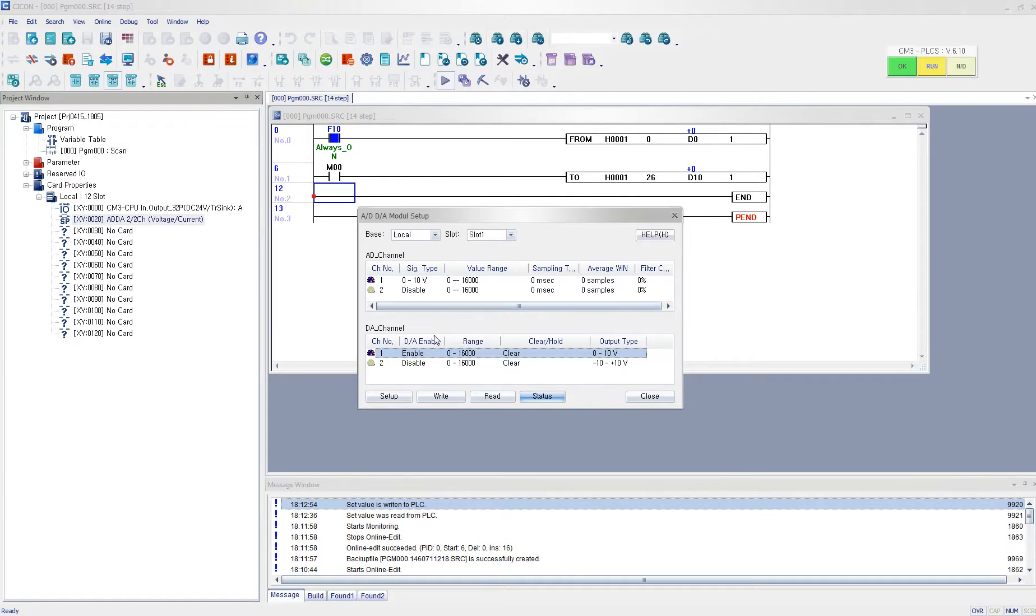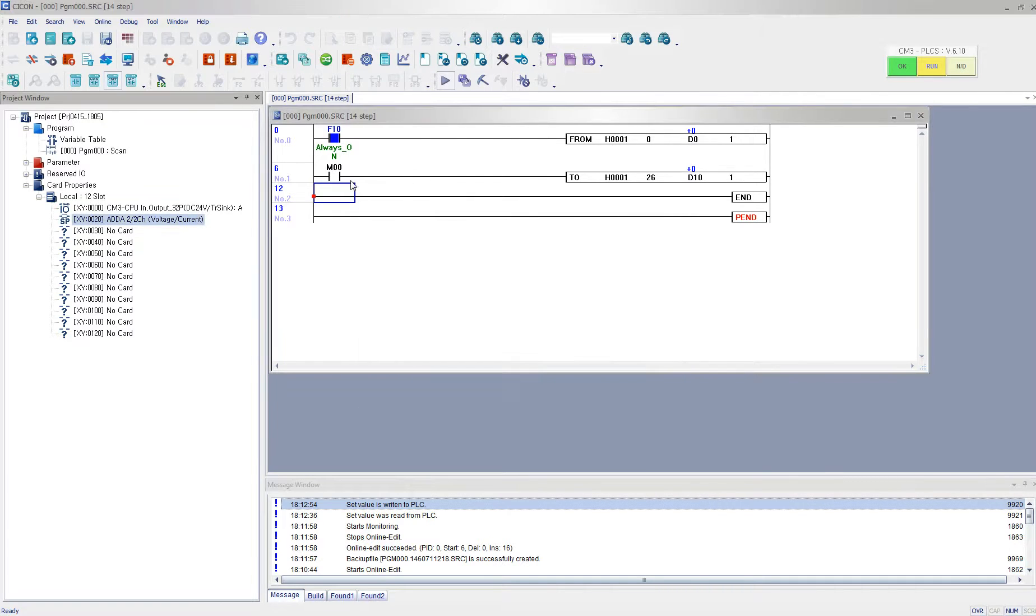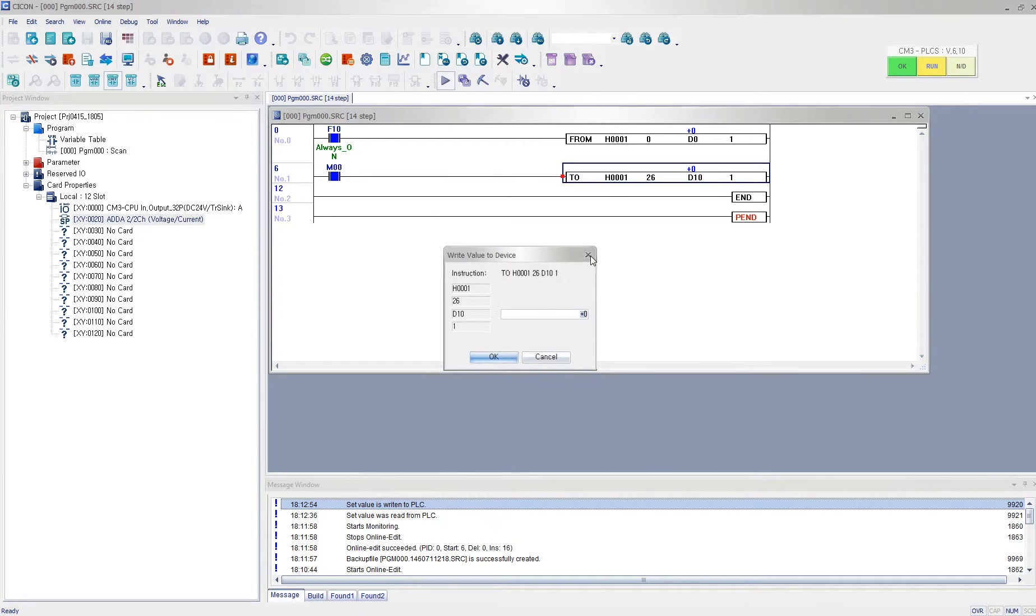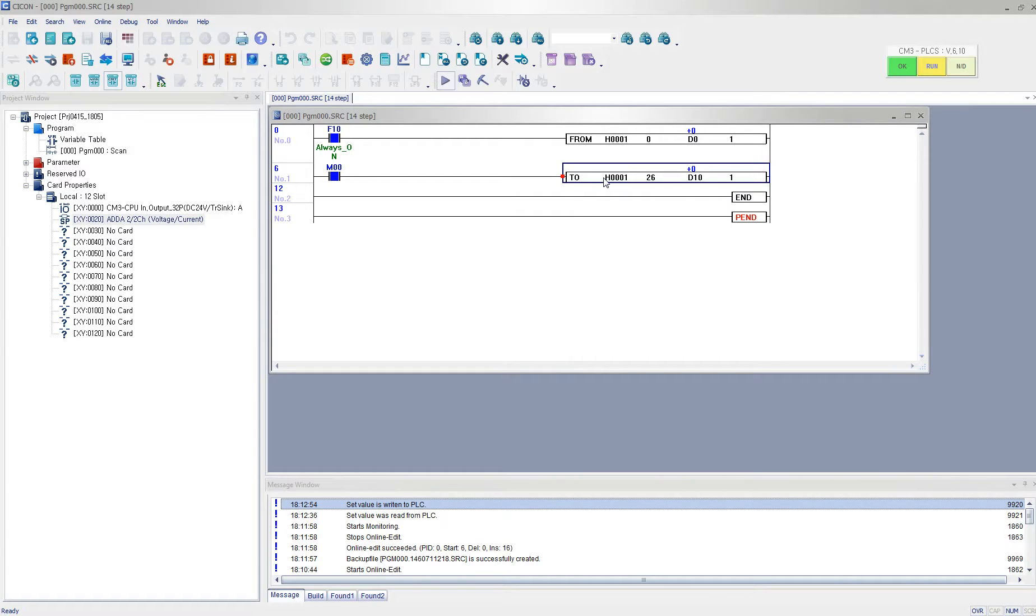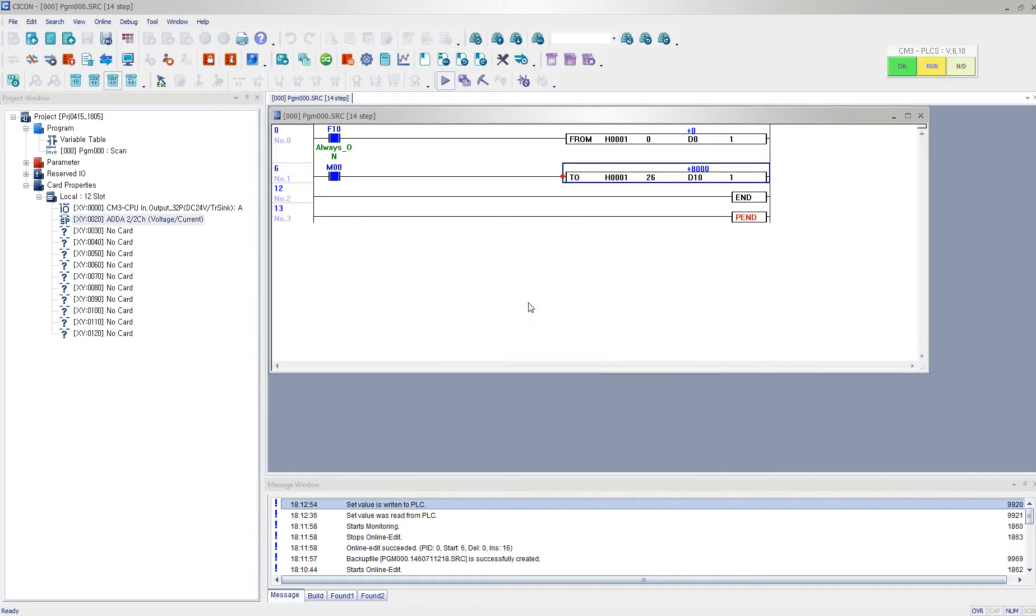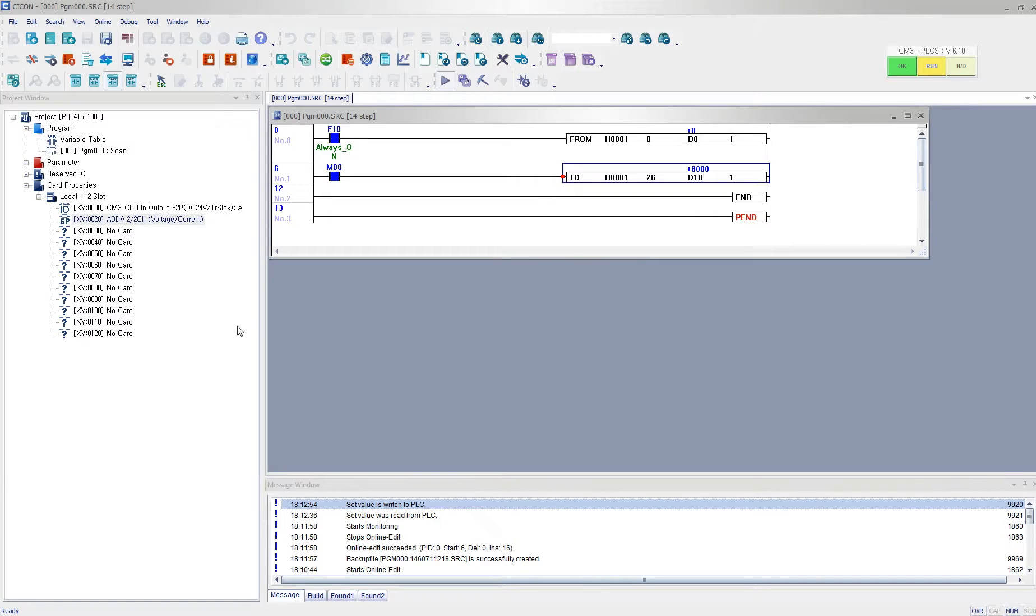So this is one way to output the desired voltage. But you can also use the TO command to output the desired voltage. What I did was you click the TO command, and then you select shift and enter and press shift and enter. Then it will show you this small dialog. And you enter your desired value. Then my calibrator right now is reading 5 voltage according to the digital range.